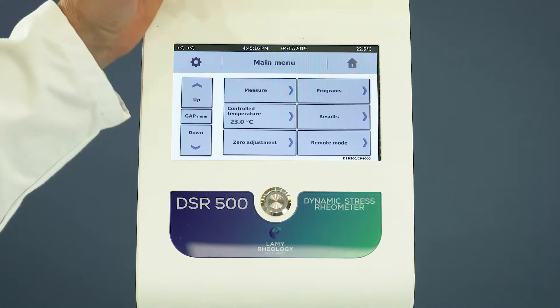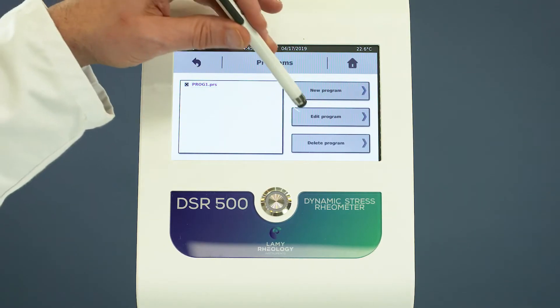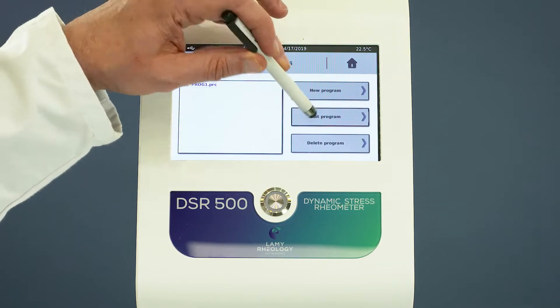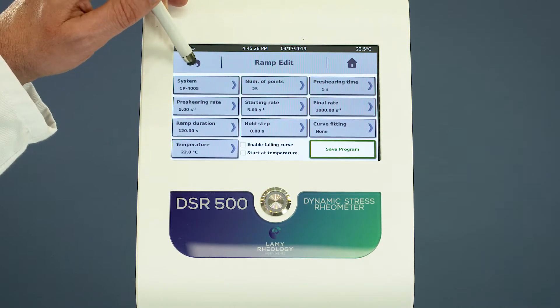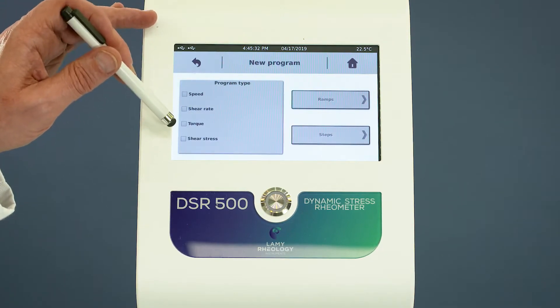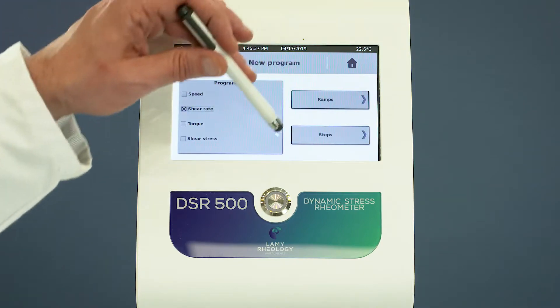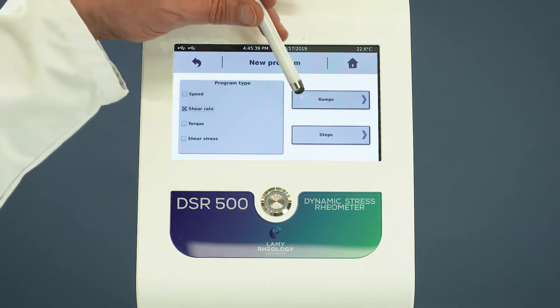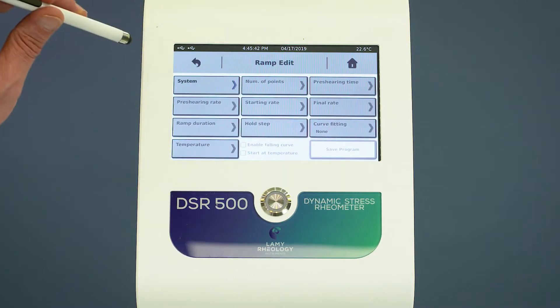Select Programs to create, edit, or delete a method. Select New Program. The rheometer can set the ramp or step program for the speed, the shear rate, the torque, or the shear stress. Select the measuring system from the list.